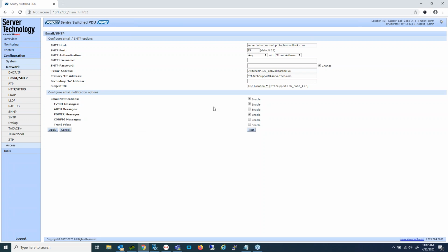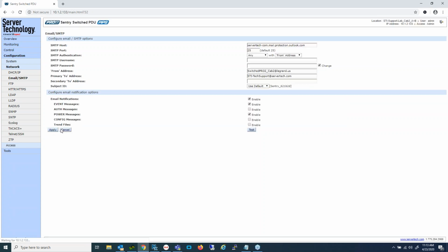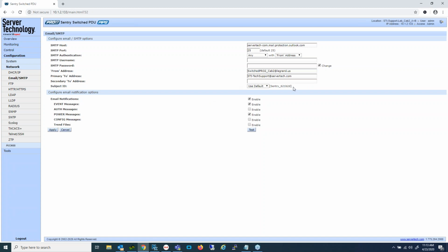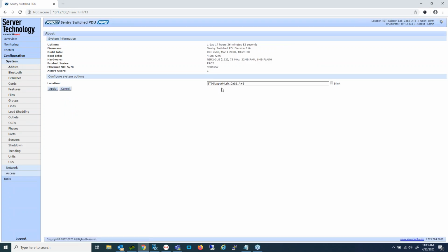What I am going to show you is event and power. Before we continue, let me mention we've got a subject ID field that defaults to a method for identifying the PDU. It defaults to using the word 'sentry' with the final 3 octets of the unit's MAC address. Alternatively, you can use location, which is a user-definable field—you'll find that under configuration, system. I've predefined the location to be an identifier showing it's the PDU in cabinet 2 in my lab.